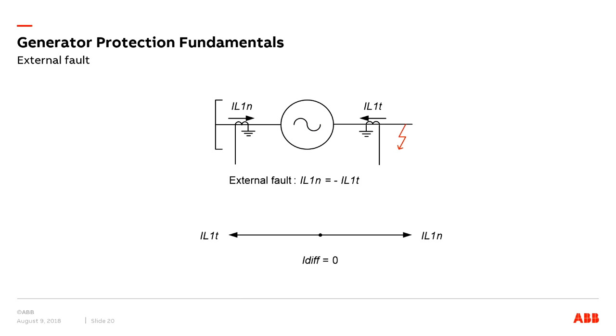Whereas in the case of an external fault, here the fault is outside the protection zone. The protection zone is defined by this area where the CTs are located, and here the fault is outside of this protected zone. The differential current is 0. At the same time, we will have a bias current equal to the phase current. Which means the protection will have good stability, which means that it will be stable against external faults. Differential protection scheme should operate only for internal faults.